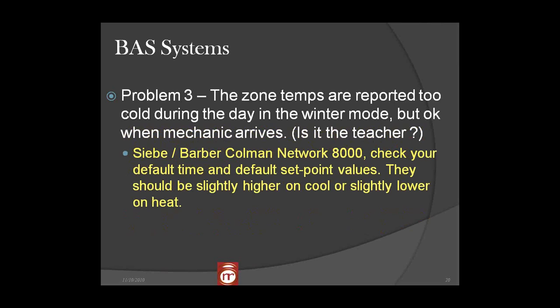Here's a good one. Problem number 3, the zone temps are too cold during the day in the winter, but okay when the mechanic gets there. And the question is, is it the teacher? Well, maybe, maybe not. In this case, it wasn't. What happened was on a Network 8000, you need to check your default times and default set point values. And basically what that says, if you lose communication, that we will maintain this set point or this heating or cooling, and the heating will be slightly lower and the cooling slightly higher. And if the mechanics know this, they know to go check the value to see if that device is talking to the main panel.